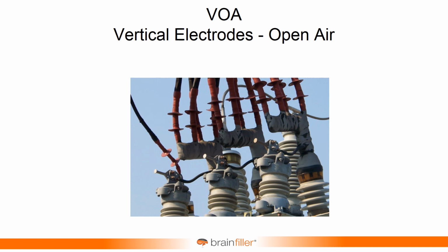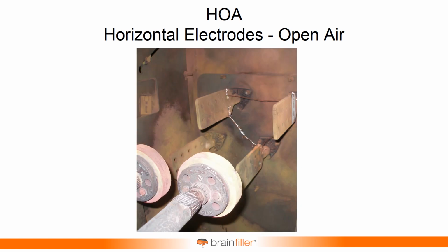And then we also have the horizontal electrodes in open air. And this is a little different. It's kind of questionable about this one because this is from the secondary of a pad mount transformer. It's a kind of a special design where the side, the top, everything opens up. So it does behave a little more like open air. But you might argue, can you really sustain an arc flash across that kind of a distance? Don't know. The more distance you have, the harder it is to sustain. But there are situations where you may have electrodes that are pointed at you. And in that case, you can use the HOA model.